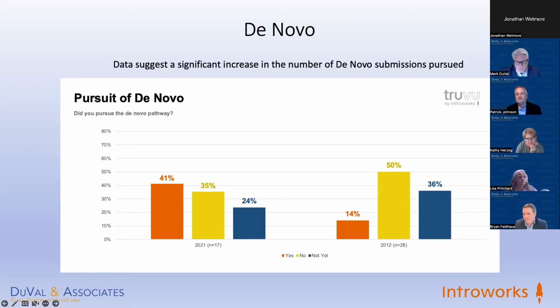And finally, to Kathy's point on de novo, when you're there, remember the data perceptions change. If you're looking on a continuum, a lot of times the reason we stay with this 510K program is the psychological reason that we want them tethered to the idea that we're very close to being a 510K, and that it should be sort of safety and effectiveness in a comparative sense. When you get into the realm of reasonable assurance of safety and effectiveness, like a PMA light, then their data expectations are going to change dramatically, and the time associated, of course, is going to change dramatically. So sometimes it's worth the fight. It's often worth the fight to stay off the de novo path. Sometimes you just have to concede that's where you're at and just bite the bullet. But anyway, just food for thought.